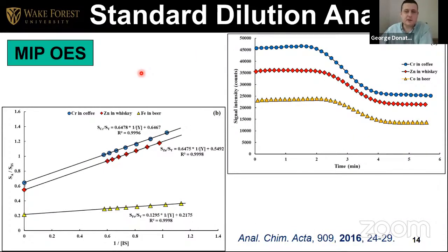Here's a more challenging application. The microwave-induced plasma has lower plasma temperature, so it is more prone to matrix effects. And in here we have several beverages, coffee, whiskey, beer, just diluting those and measuring directly on the microwave-induced plasma by optical emission. So it's a very bad situation in terms of matrix effects because of the low temperature of the plasma and because we're not digesting anything. And you can see the calibration is very linear again. And here's the profile of the signal. Before we add the second solution, around here, the signal goes down and we use those points there. You can note that we have fewer points now when comparing to the ICP-OES because the microwave plasma is a sequential measurement. So it takes time going from one analyte to the next. So in time, the dilution is happening.